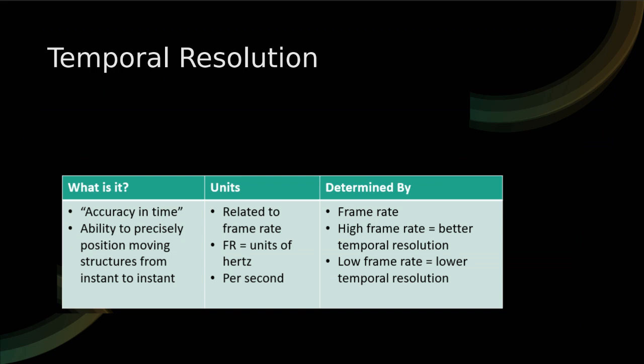When talking about frame rate, it's important to touch on temporal resolution. We learned about axial and lateral resolution — those refer to the system's ability to display individual structures located a particular distance from each other. Temporal resolution is different: it's the detail we get in reference to time. It's known as our accuracy in time — the ability of our system to precisely position moving structures from instant to instant, allowing us to visualize a fetal heartbeat, a pulsating aorta, or blood traveling through a vein.